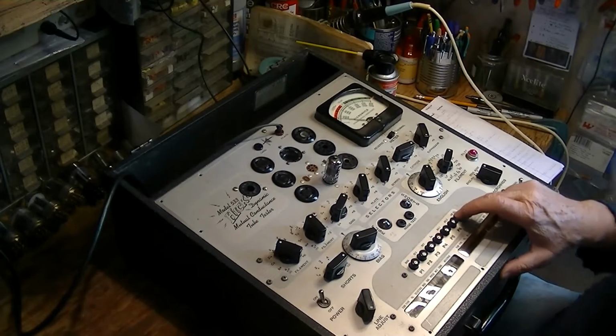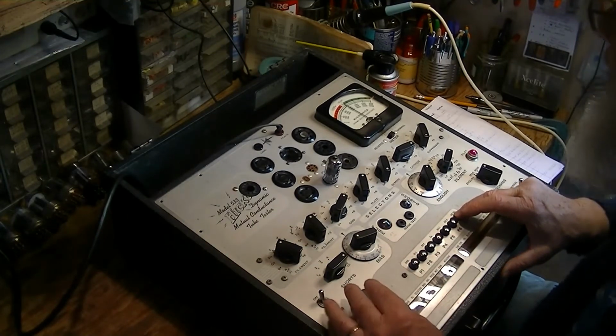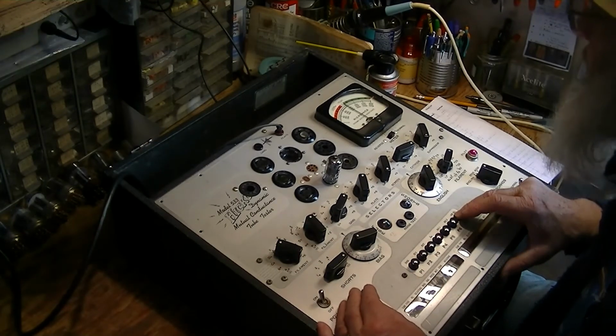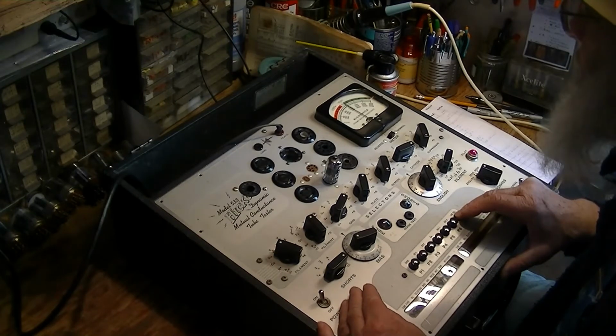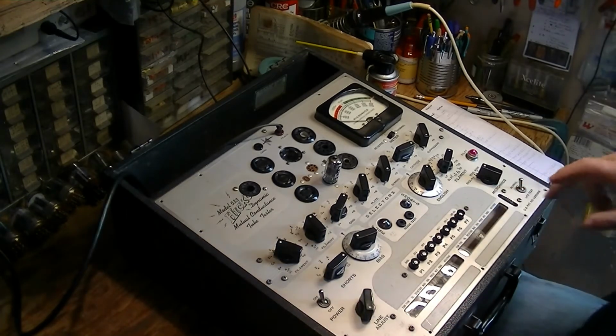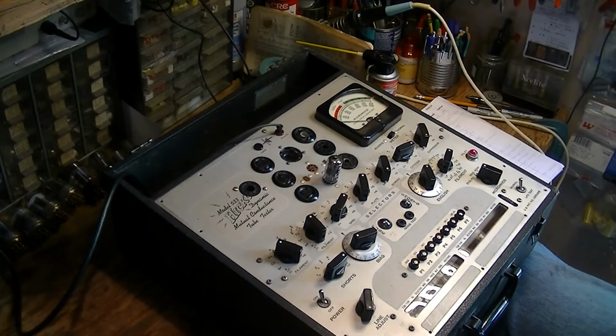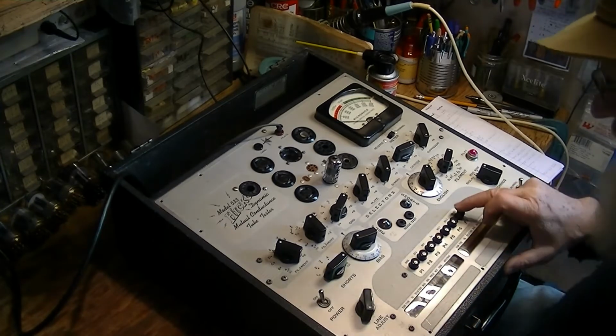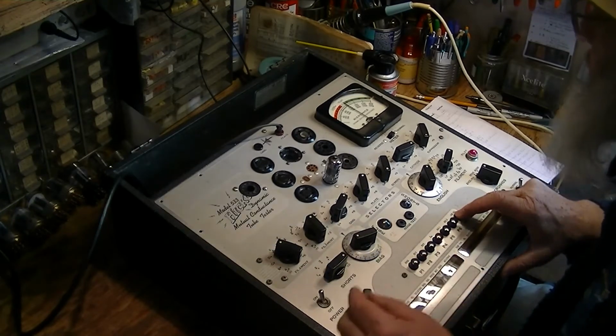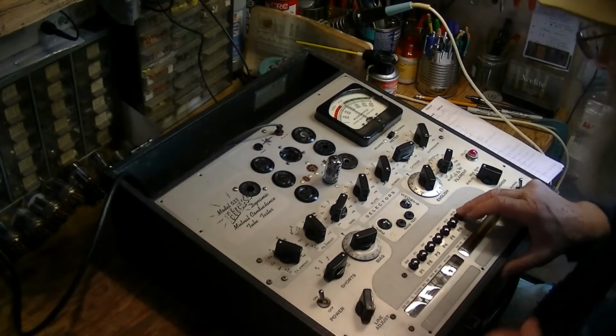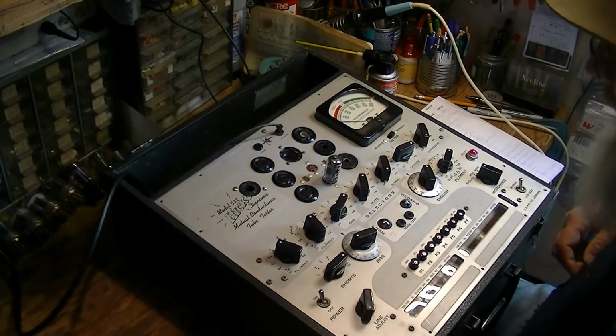Go back and check my line adjustment. The line adjustment has dropped again under this different load for different filament. This is something you'll see if you put in a tube with a heavy filament in it, like a rectifier, one of these 6146s. It can cause the line meter adjustment to go down quite a bit. So you want to check this every time before you start checking your tubes. So we're all set there.